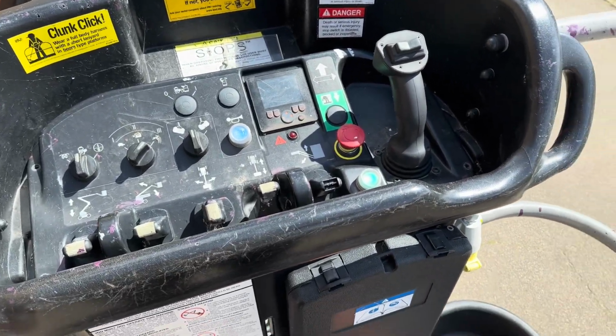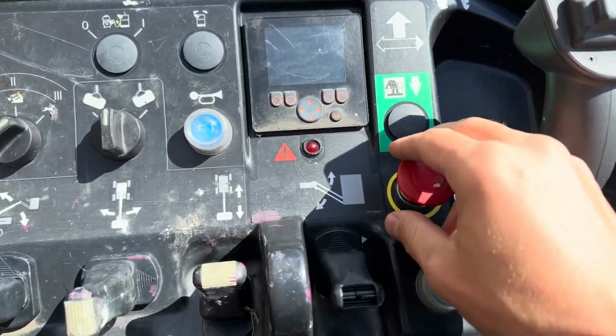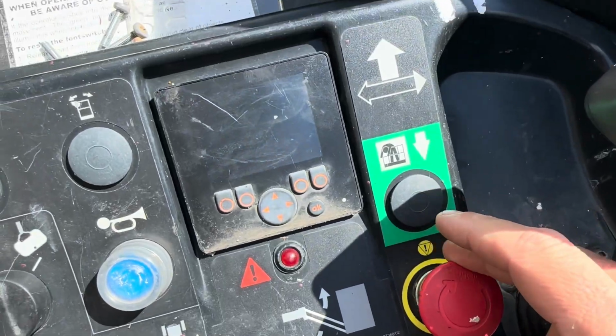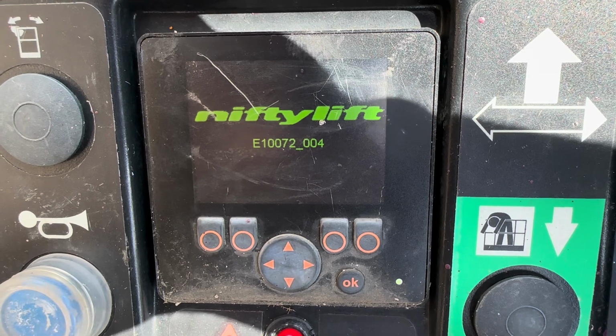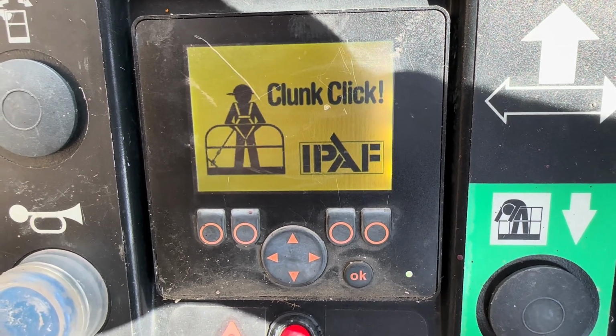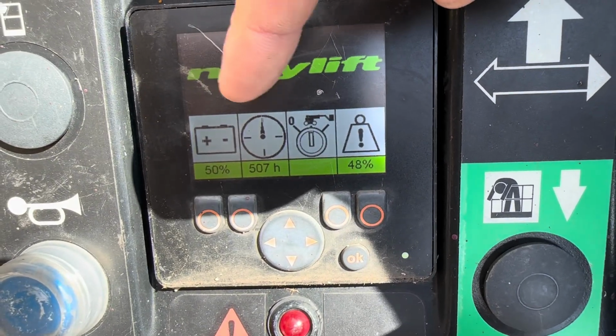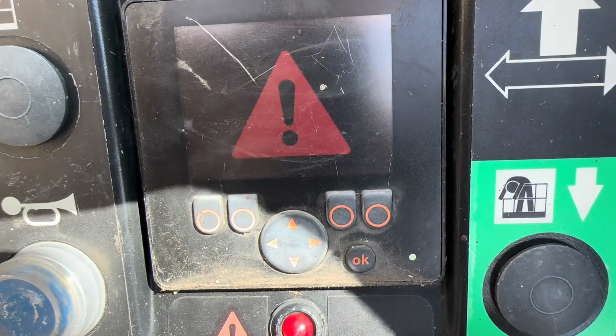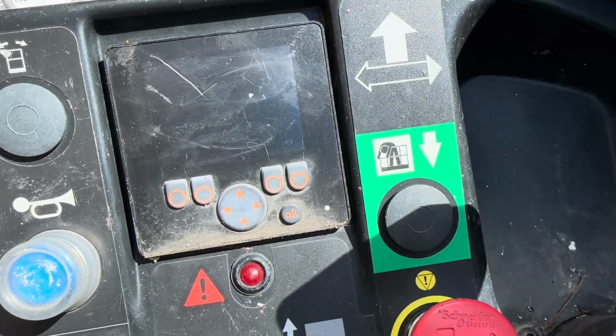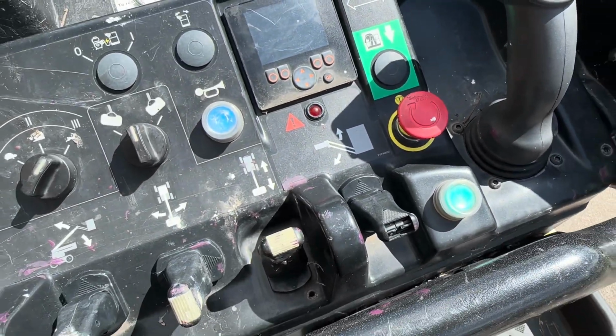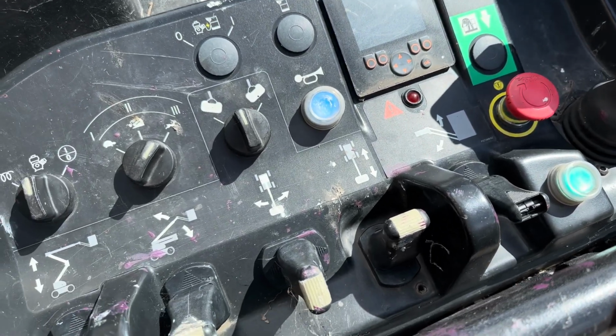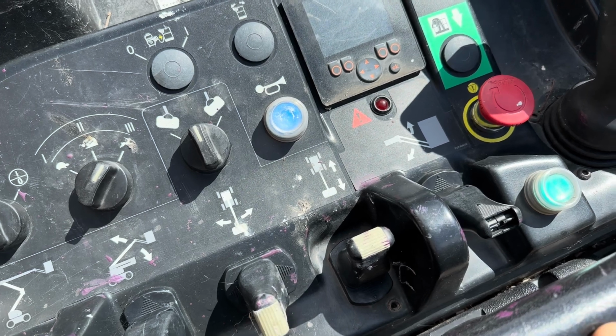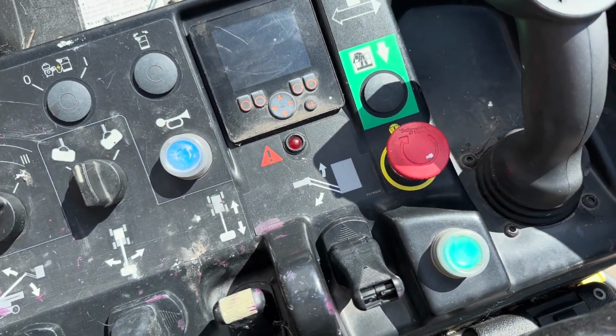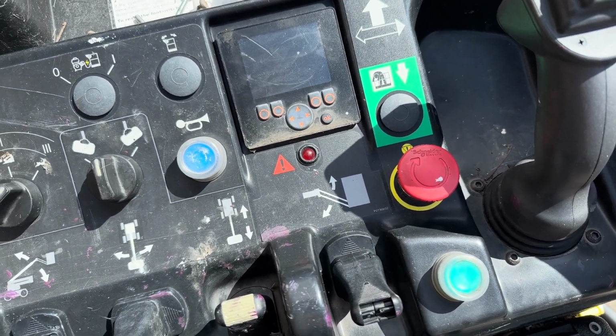It is HR17 and we have an overload fault. If I enable the machine, you will see on the screen it starts, shows 50% on the weight, and then it goes into overload. So if I look in the calibration, I see 0 kg on one channel and the other channel about 20 kg.